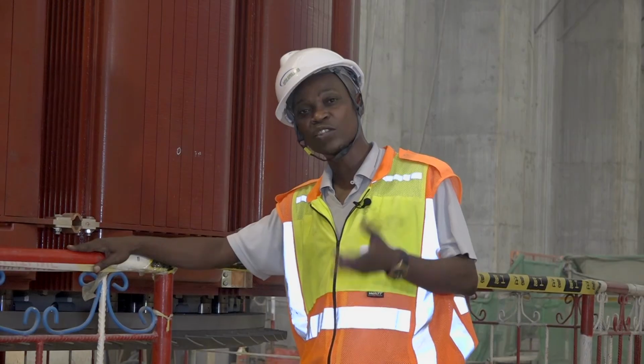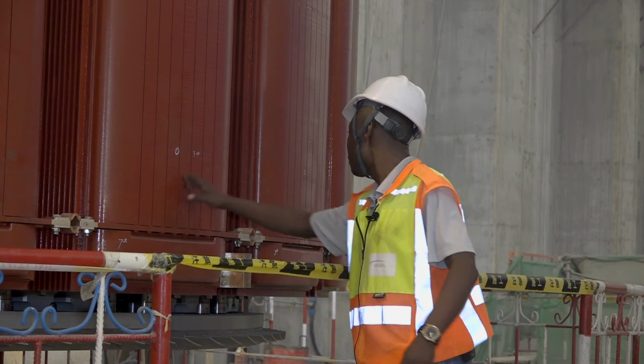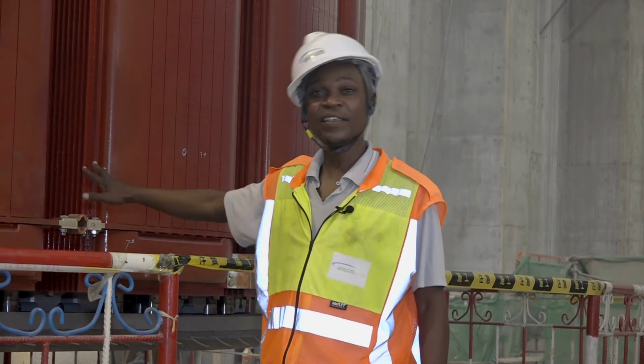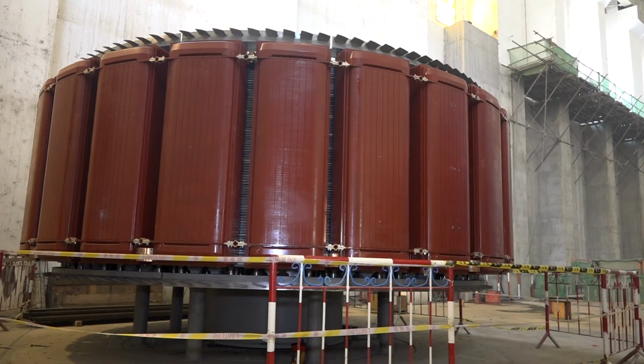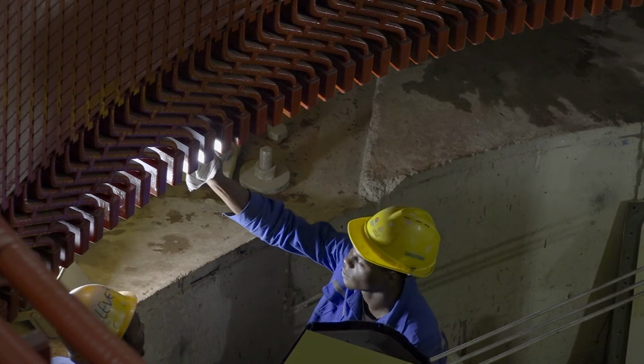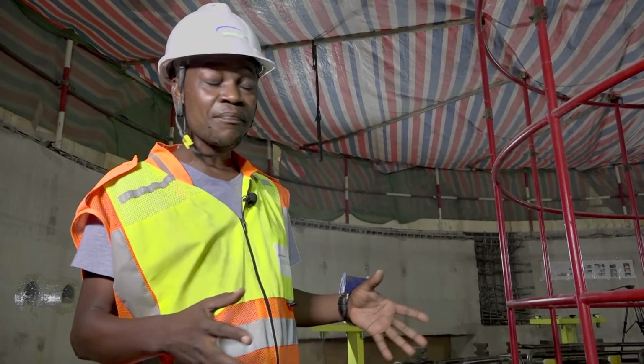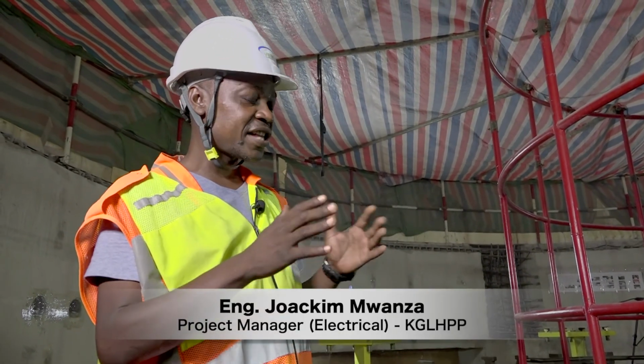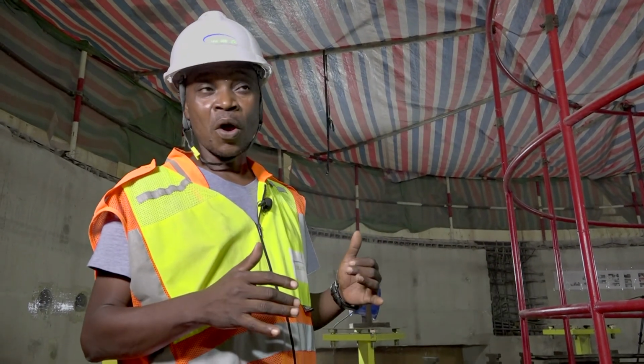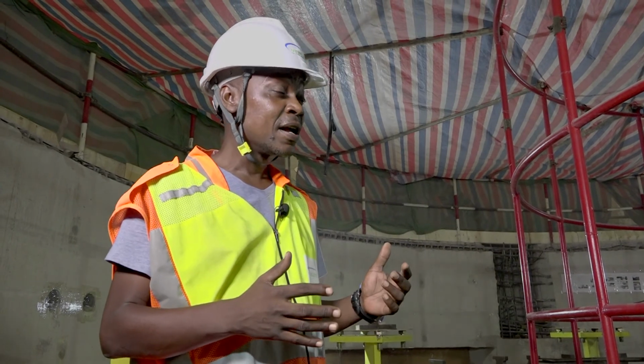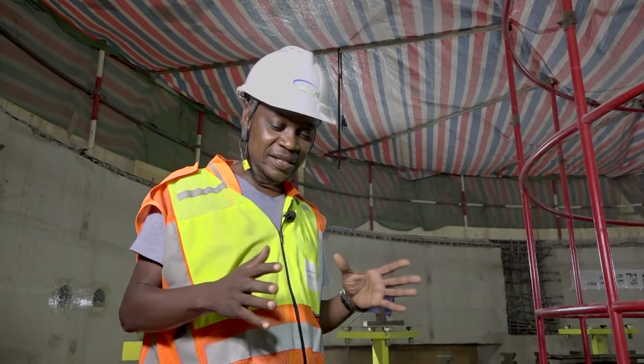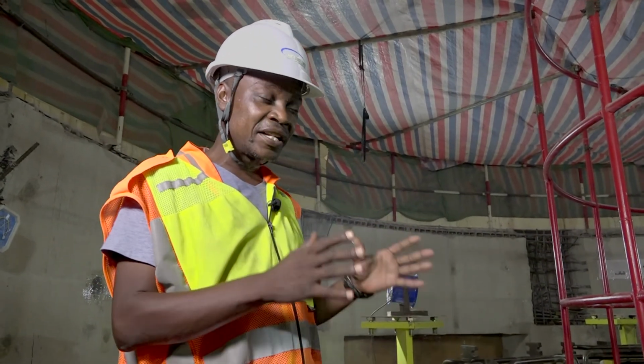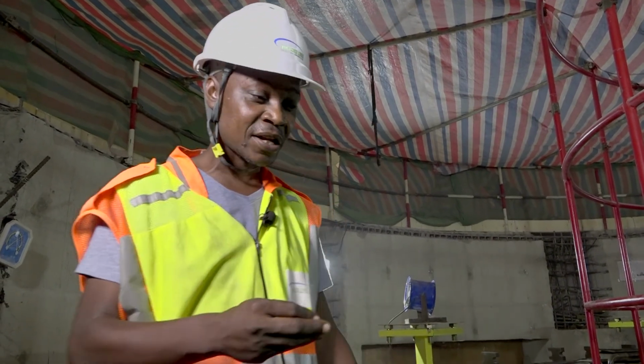So for our machines at Kafue Gorge Lower, each rotor comprises of 24 poles. These are the poles I'm talking about, and the windings. So for unit 1, the rotor pole is already complete and ready to be lowered into the pit. As we assemble the stator or even the rotor, it is important that at any stage you carry out some tests. We do electrical tests and mechanical checks, because if you miss to check the integrity of your assembly, it can be a costly and time-consuming exercise.